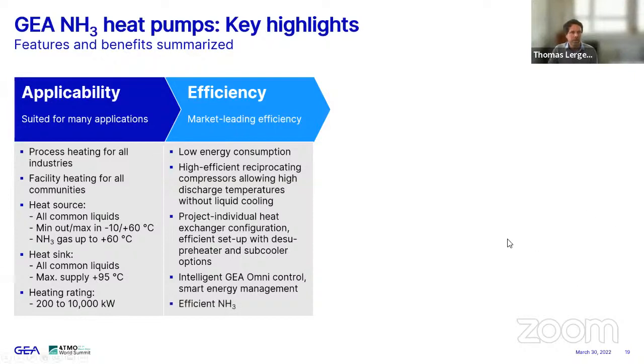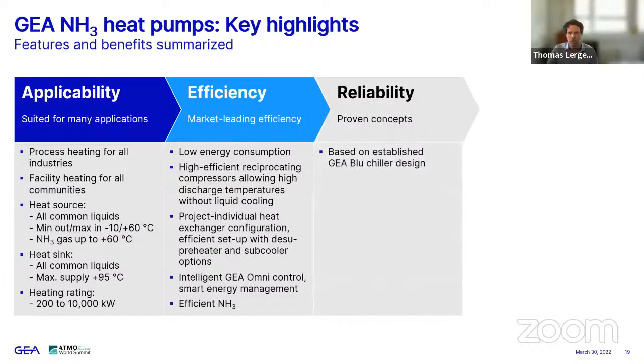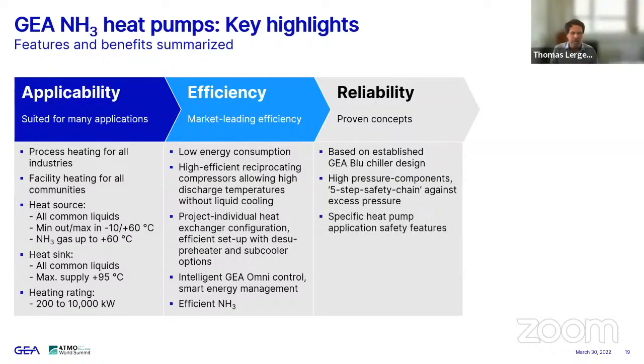And reliability is an important factor. Our heat pumps are based on proven concepts, on the established GEA Blu chiller design. Of course, we're using high pressure components. Each unit has a 5-step safety chain included against excess pressure. On top of the established chiller design, there are more specific heat pump application features to increase safety, for example, to prevent condensation in the compressor because of low machine room temperatures and high suction and evaporation temperatures. Again, the Omni control is very important for the reliability. It includes predictive maintenance functions, and a lot of experience from hundreds of heat pump installations in the past 10 to 15 years.